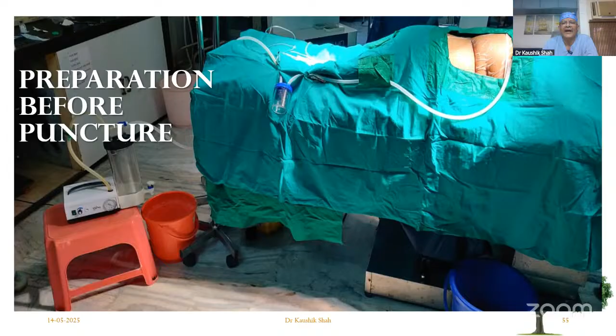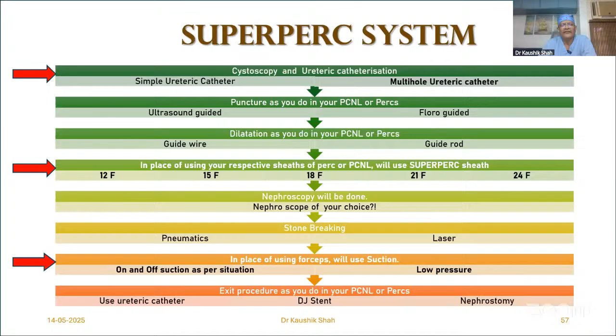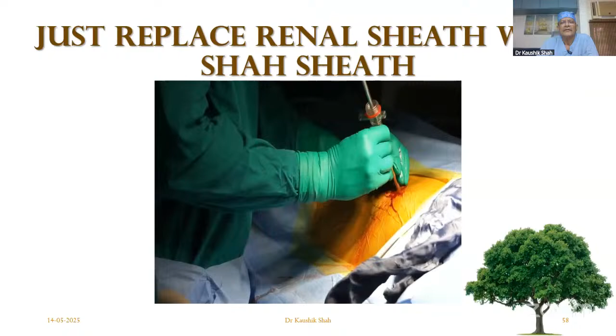So the SuperPerc system requires only three changes. One, if you want to use a simple sheath, it's all right. Otherwise, you can use a multihole ureteric catheter. It has a number of advantages which I am not going to discuss today. Plus, whatever sheath size you want to use, instead of a regular sheath, you use a SuperPerc sheath. And whenever you want to use a forceps, don't use the forceps, use suction, and all the fragments, multiple fragments, can come out simultaneously.